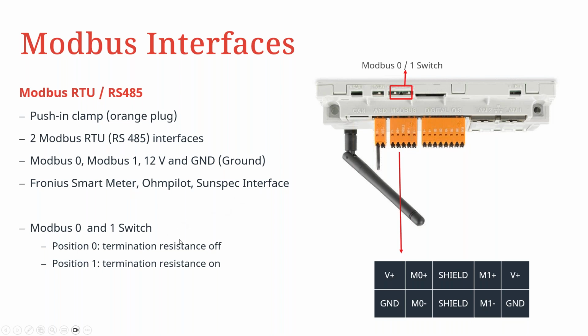And then additional information about this switch is that putting it on position 1 actually turns on the internal and integrated 120 ohms resistor. Basically, for communication to take place, there has to be a closed loop between the receiver and the transmitter. So this 120 ohms resistor serves as the loop terminal. That is basically the loop closer, per se, the component that closes this loop for efficient communication. So there has to be this 120 ohms at the end of the communicating devices.